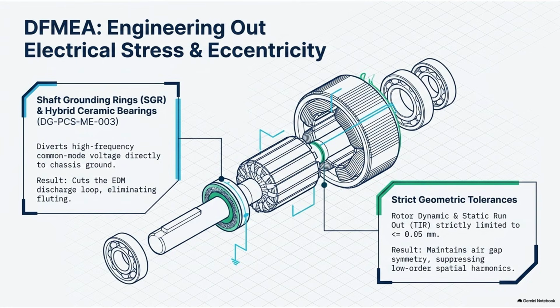Right. This brings us to the actual mechanical and electrical engineering blueprints. The DFMEA, right? The Design Failure Mode and Effects Analysis. Yes. How do we build a motor that is immune to its own physics? So the first mandate is obvious. You have to deal with that high-frequency shaft voltage. You have to ground the lightning before it hits the bearing oil. Exactly. The design specification here, DG-PCS ME003, mandates the use of a dedicated shaft grounding ring, an SGR.